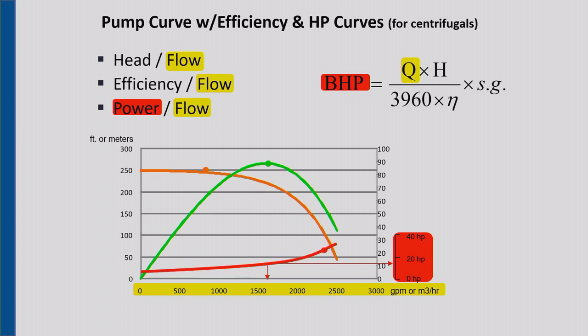Okay? This was an interesting experience for some plant mechanics working on a pump. Installed a new pump, started it up, checking the motor current, everything looks fine. He says, okay, let's load this thing up. I want to see what it does when it really gets working hard. And he closes down the discharge valve. And the pump starts going and starts making noise, and they're really loading it up. And what happened to his amp meter? It went down.